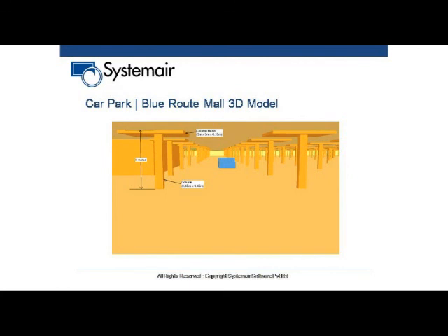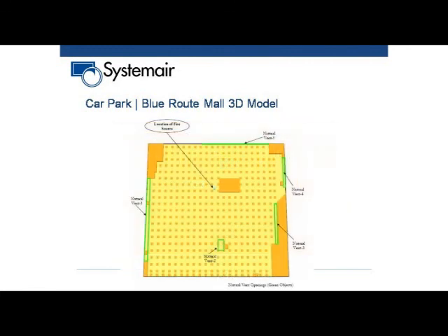This was the 3D model. We modeled the drop beams, everything. This was the 3 meter height, and all the columns were modeled. This was the car, the source of the fire, the location of the fire, with natural vents all around. And when we did this, okay, there's some problem.